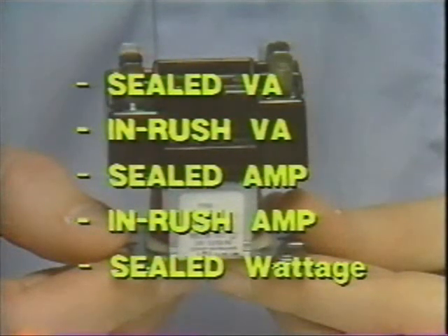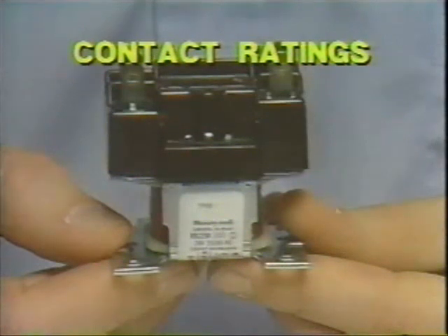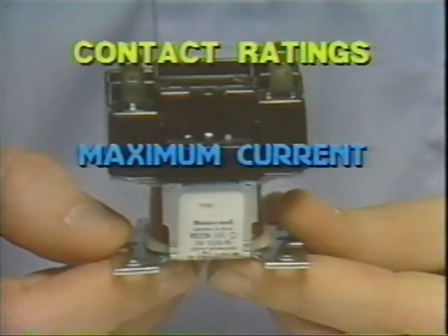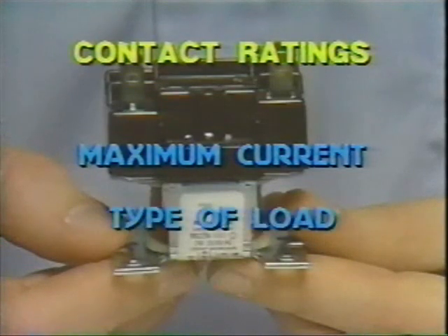Coil ratings which use these terms include nominal and maximum sealed VA, nominal and maximum inrush VA, sealed and inrush amperes, and sealed wattage. The term VA stands for volts multiplied by amperes. When it comes to contact ratings, the most important things to know are how much current the contacts can handle and the type of load the rating applies to.